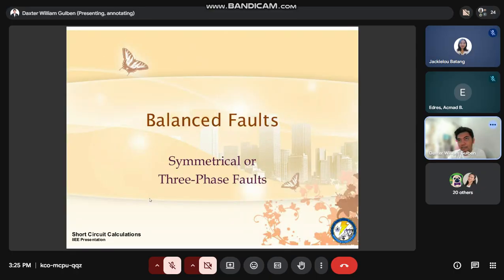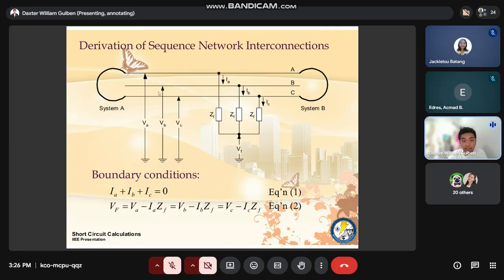Now let's go to the shunt faults. There are four shunt faults. The first one is the balanced fault, or what we call the three-phase fault. What are the cases of this three-phase fault? Your three lines are hit by a falling tree, either directly connected to the ground or the tree itself creates a direct connection of the three phases to the ground. For example, here, phases A, B, C have an impedance developed, the tree stuck on the lines and its root was not removed. So the impedance is ZF. In the boundary conditions, IA, IB, and IC must sum to 0. These are the faults.